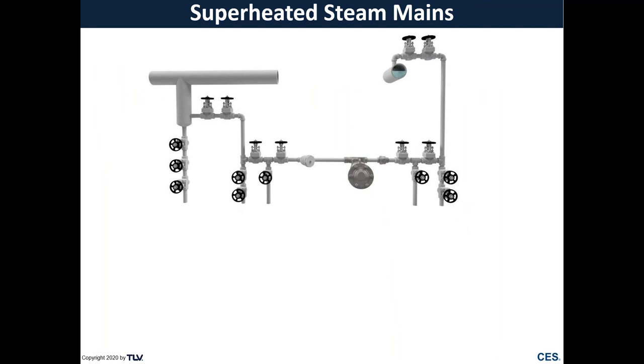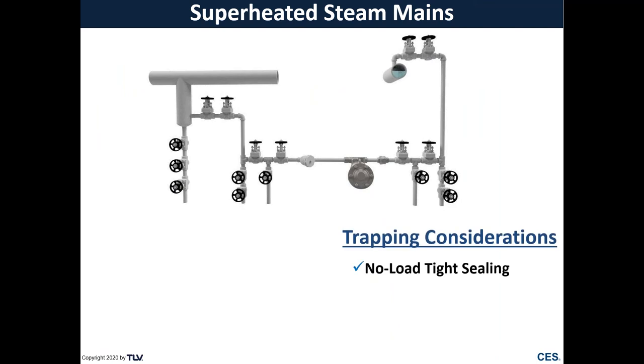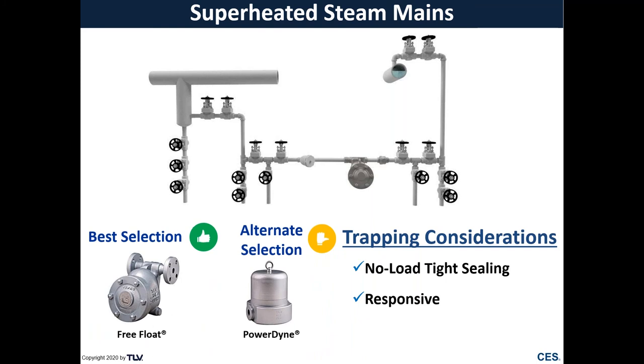So our trapping considerations here are that you need a trap that is going to provide a tight seal even under a no load condition, as well as something that's going to be responsive to any type of upset. So here your best selection is going to be something like a 3-point seated free float or one of our high pressure thermodynamic Powerdyne disc traps.